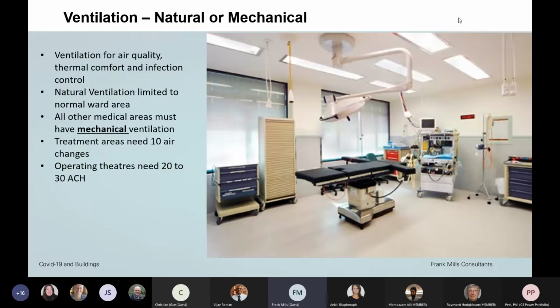10 air changes, in simple terms, mean that every 6 minutes we replace the air in the room. Now, because the air is mixing all the time, that's not what actually happens - what happens is we dilute the air. So at a rate of 10 air changes, it would take around 28 minutes to actually replace the original air. It's a case of keeping the dilution factor going. In more important areas such as operating theatres, we work to much higher air change rates, typically 20 or 30 air changes an hour.